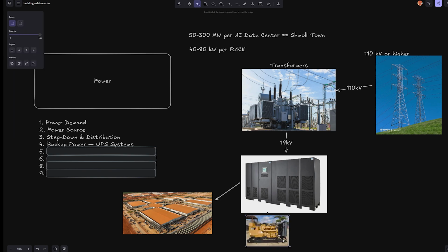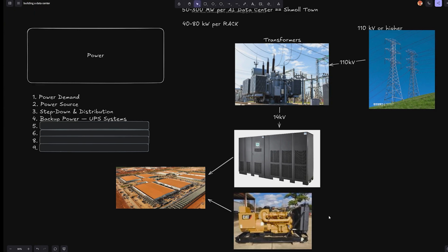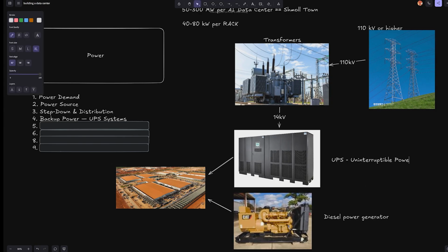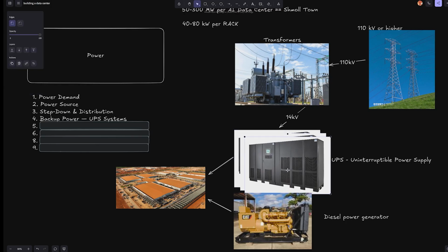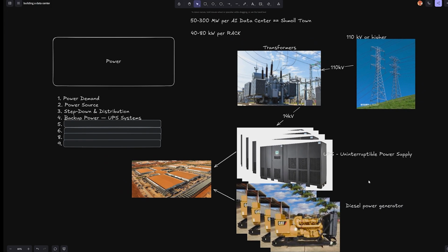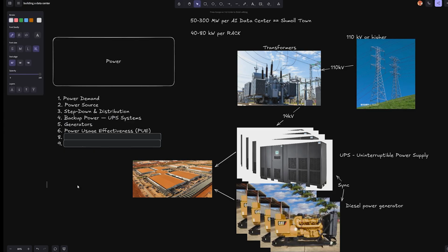So the generators, rows of diesel or gas generators that stand by outside the building. They can keep the facility running for hours or days depending on the fuel storage, and they have an auto start and sync system with the UPS within a few seconds of power loss. A perfect data center would have a PUE, or power usage effectiveness metric, of 1.0. But traditional centers often hover around 1.4, and the more optimized ones between 1.1 and 1.2.